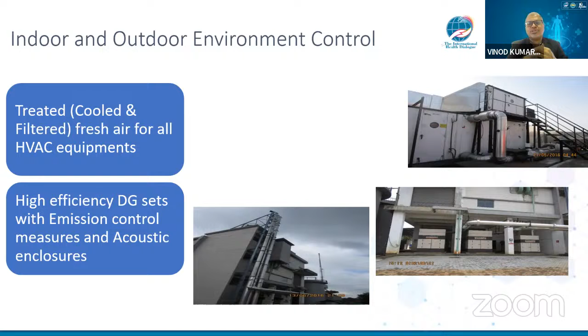This generally doesn't happen properly, because bringing in fresh air increases the chiller load and energy consumption. So generally the fresh air system stays closed, but you can't have it in a closed system—you need fresh air as per healthcare requirements, and you cannot bypass that. The only way is to keep the fresh air systems open and properly working, so contamination control happens as designed. Otherwise, you'll have contamination issues if fresh air is not used properly in the hospital.